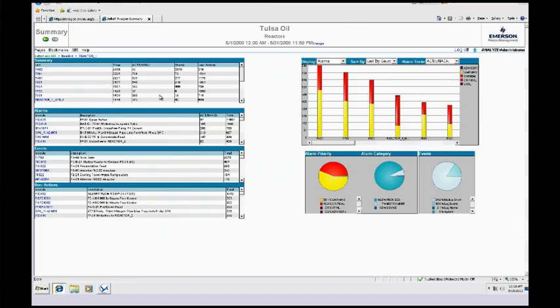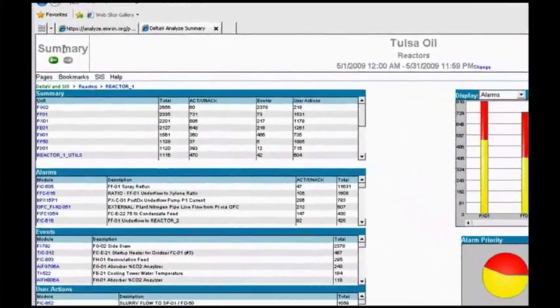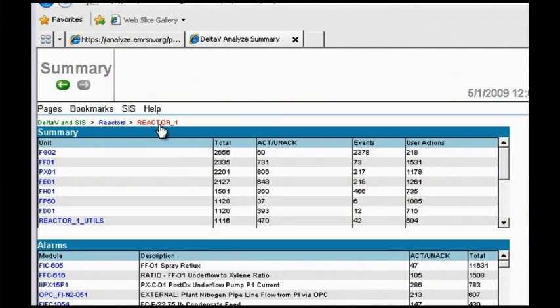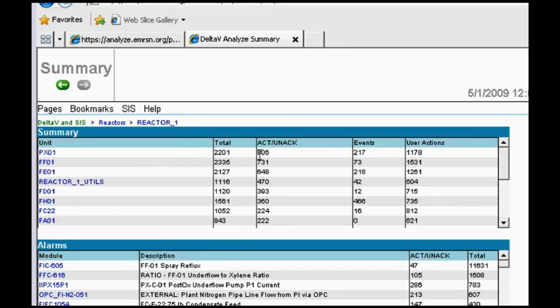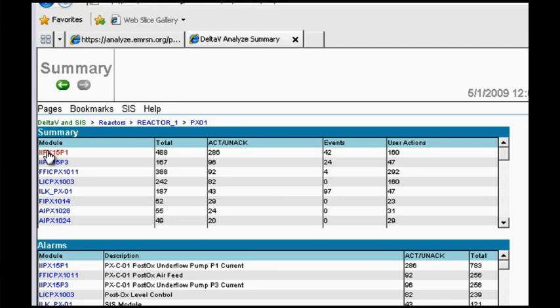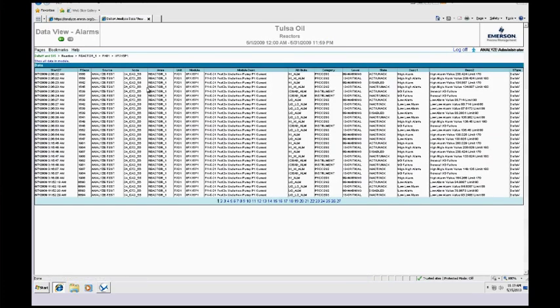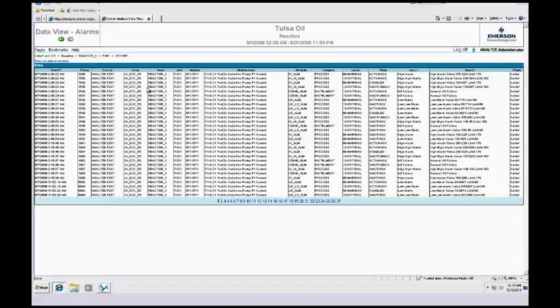We've moved to a new page, the summary page. And we're currently looking at reactor one. Let's go ahead and drill down and find out where the number one alarm is in terms of alarm frequency. So to do that, let's go ahead and sort our list here such that all of the units in the plant are in order of incoming alarm rate. This PX01 unit had the most alarms within the reactor one area. And within this area, this module had the most alarms. Within this module, this alarm occurred with the greatest frequency. And you can even quickly get down into the raw data. So as you can see, it's very easy to drill down into Delta V Analyze to identify a particular alarm of interest.